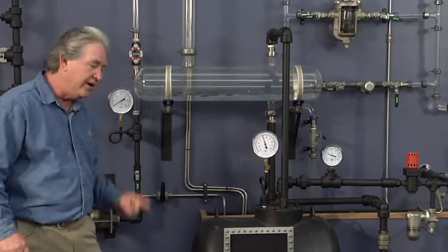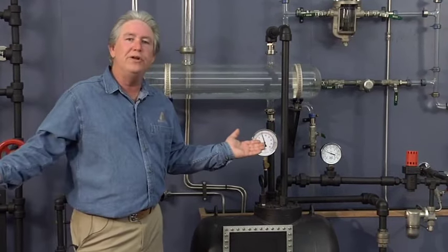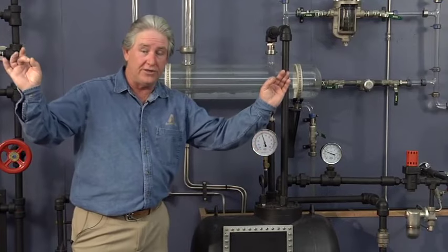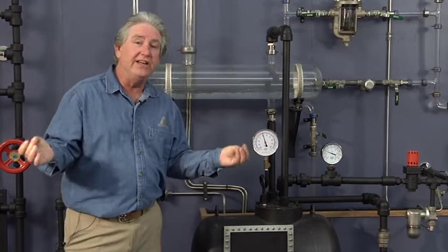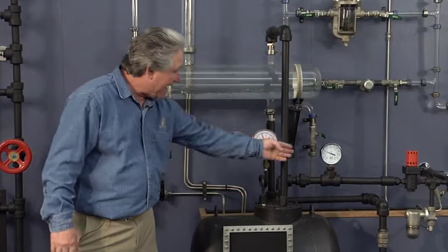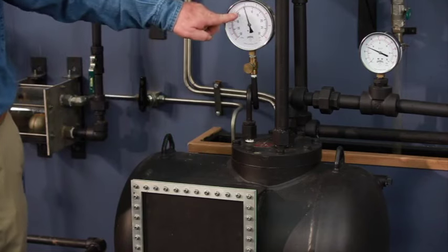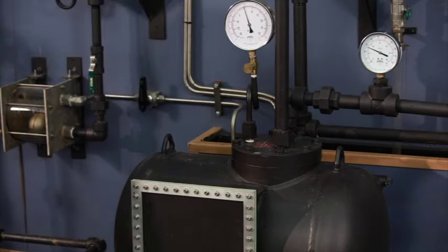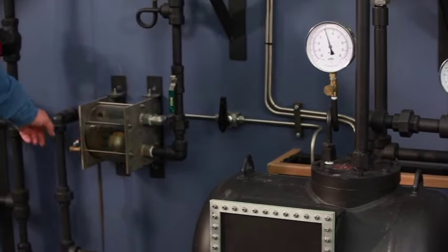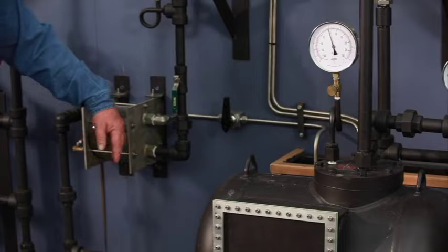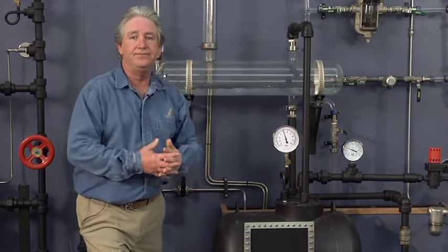It's already moving. Remember, we had no differential pressure. We were stalled. We're inducing differential pressure now by the high pressure feed into the pump, pressurizing up over the back pressure, coming in, pushing it out through the float trap and up into the header.